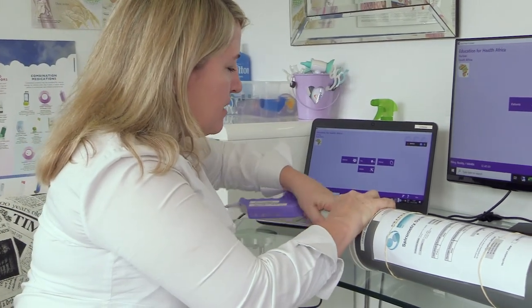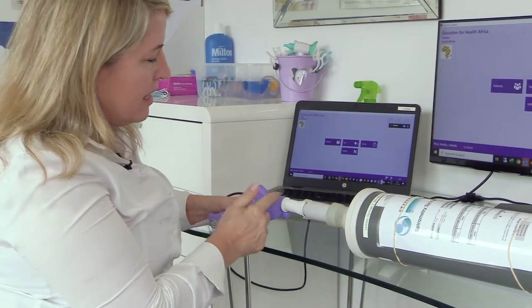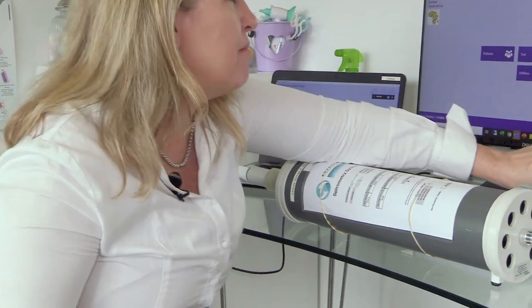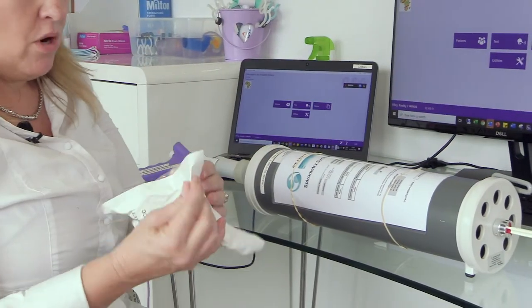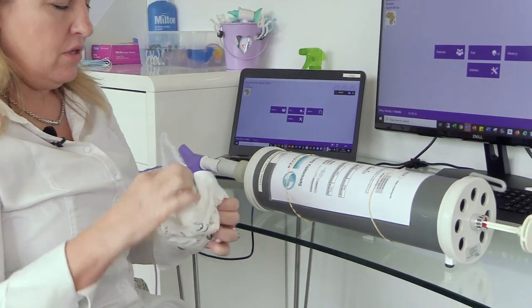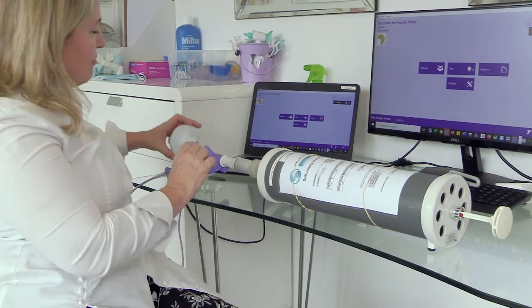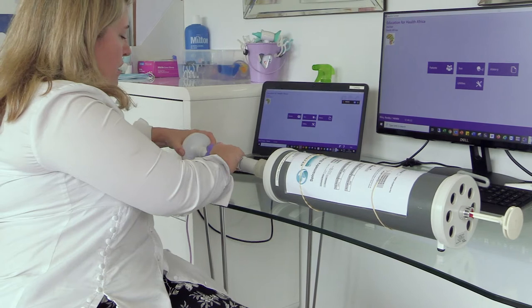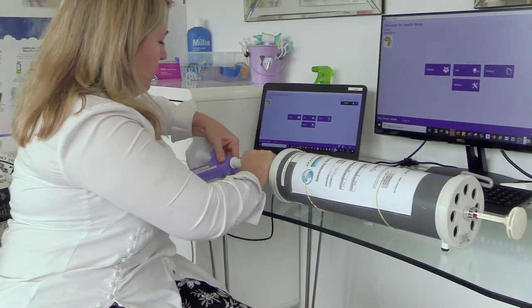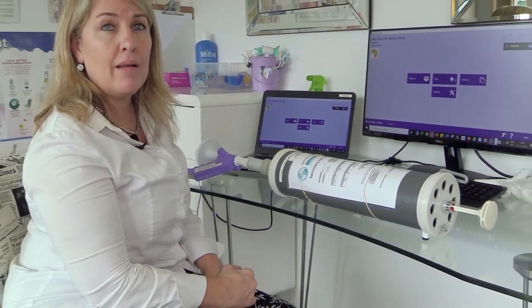Now I'm connecting it to my syringe, making sure there are no leaks anywhere in the circuit. In the time of COVID, you might need to calibrate using the bacterial filter that you're going to use at the time of testing. In this circuit it fits on the back here — I'll just connect it up. I now have my circuit all ready for the calibration check.